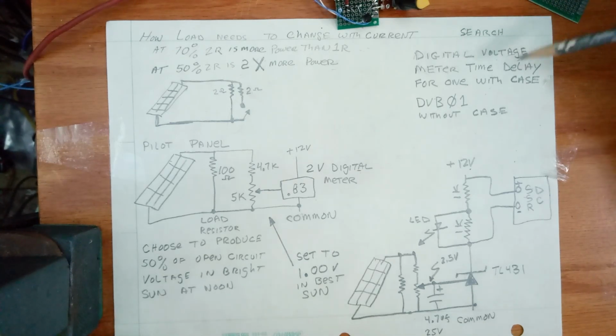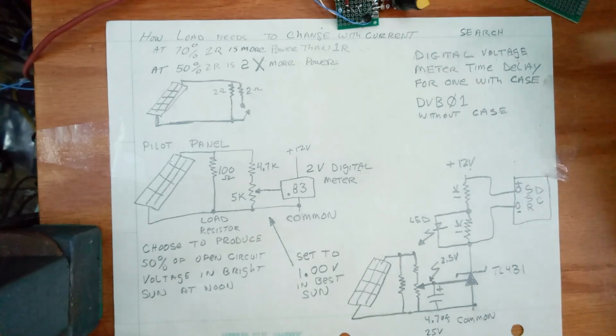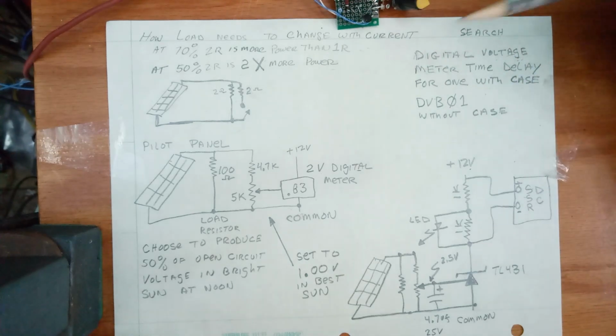So that's a nice turn-on range. And you always want to put in a time delay. These bricks are nice, but they're slow. So at least have a 1 minute time delay between turning them on and off, because if you're switching back and forth, these relays will heat up. So that's my suggestion.